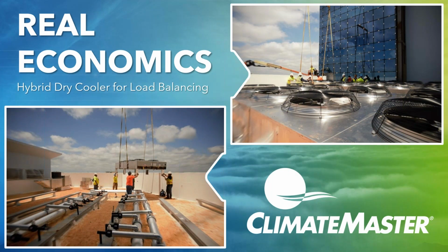You'll notice on the slide there were some additional items included in this project: dry coolers that were designed not to provide any benefit to the heating or cooling load of the structure. These are designed to maintain the ground temperature around the earth loops. They're somewhat limited because all the ground loops are installed vertically and are beneath the parking area. So rather than expanding that loop field, these dry coolers were installed, and they only operate when the ambient temperature is below 48 degrees.